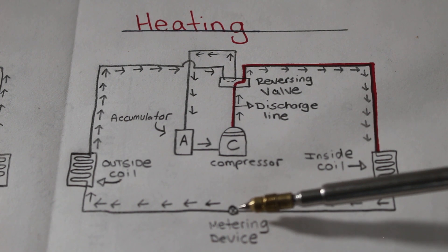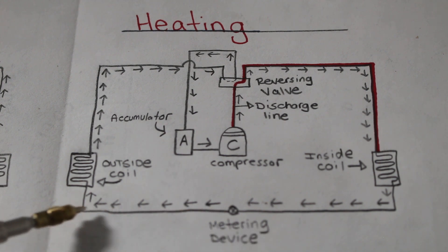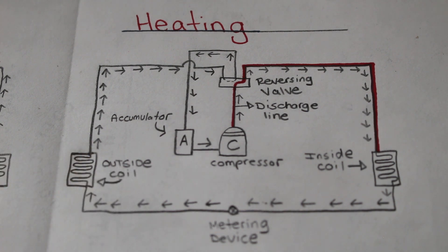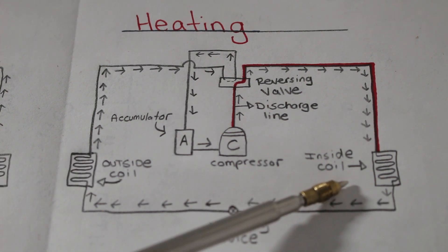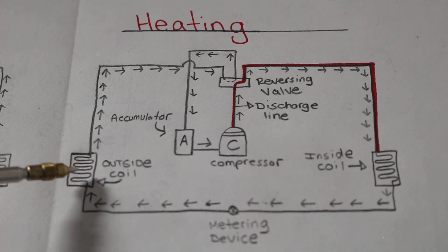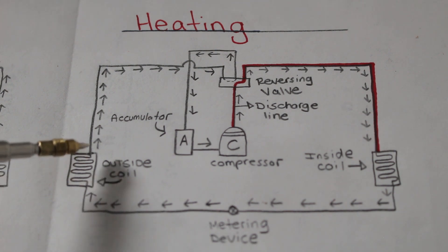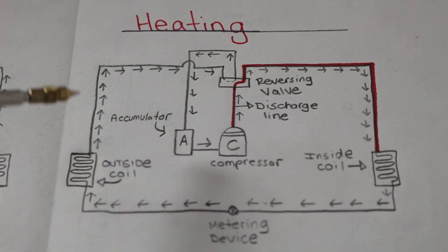We enter our metering device, where we have a drop in pressure. We continue along and now enter our outdoor coil, which is now our evaporator. So we're going to be blowing cold air outside, and inside we're going to be blowing out warm air. Entering the evaporator, at about midpoint of the coil, we have latent heat of vaporization, and we change from a liquid back into a vapor. We exit as a low-temperature, low-pressure superheated vapor.